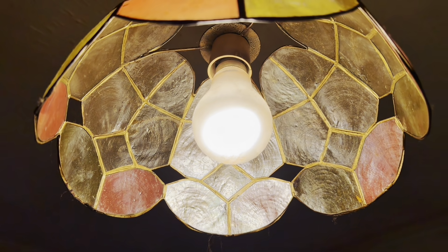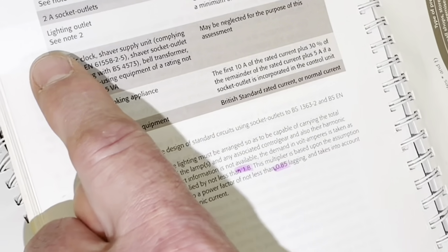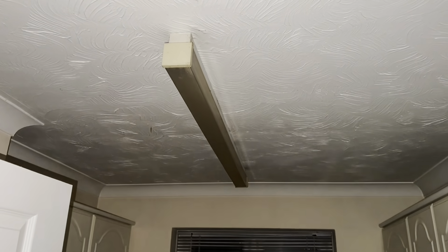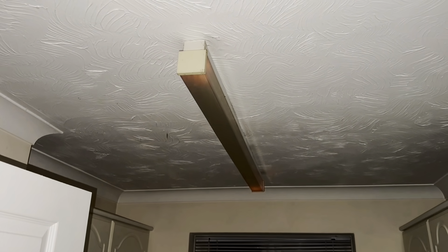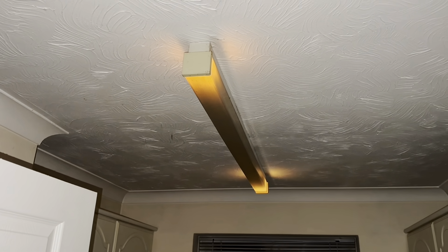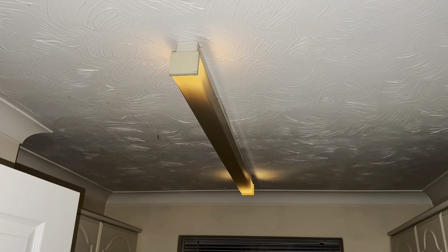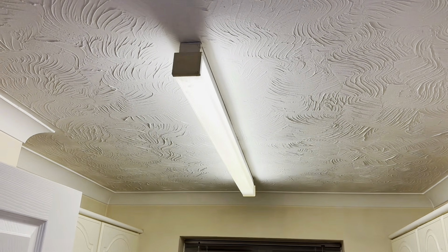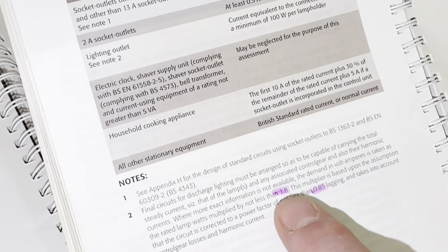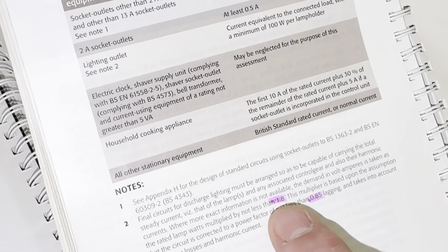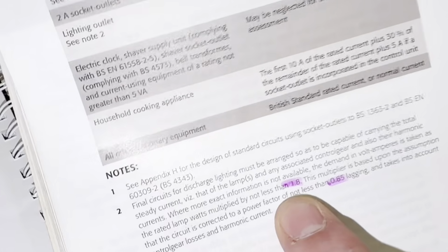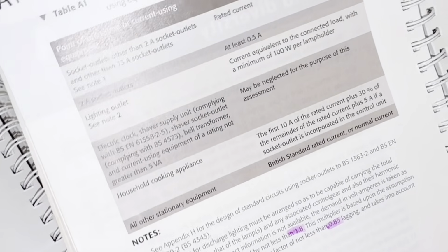There is a separate note here which talks about discharge lighting. So where you've got, say, a fluorescent light fitting in a kitchen, you turn it on, you wait what feels like an eternity for it to strike. They've got what's called a choke or a ballast within them, which creates a lagging power factor. So it's suggesting where there is a lagging power factor of around 0.85, you must multiply the lamp wattage by 1.8 as a correction factor. So they've been replaced as well, but let's go and jump forward in time.